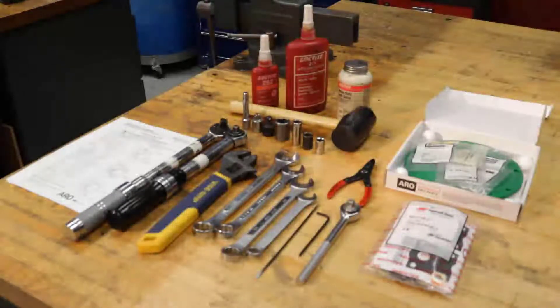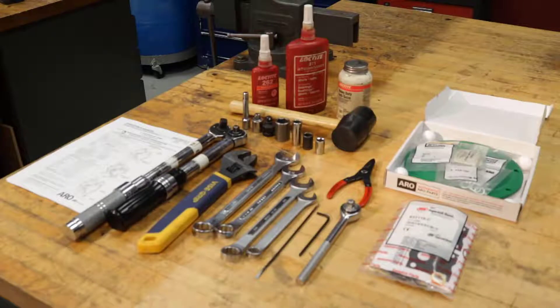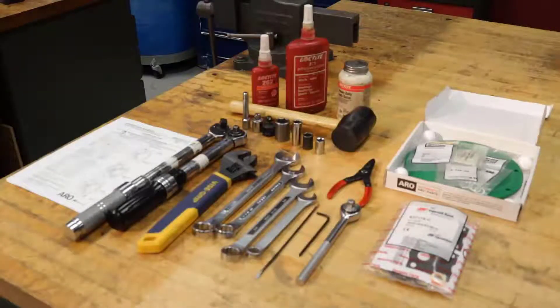Hello everyone, this is Justin and Bruce with ARO Fluid Handling Technical Support. Today we're going to be repairing a 1 inch metallic Pro Series pump. We are going to be converting a Pro Series pump with nitrile balls and diaphragms to a PTFE ball and diaphragm material. We're going to need the appropriate tools along with the appropriate Loctite and anti-seize, and you want to make sure that you always have your operator's manual and that you're using authentic ARO parts. Today we're going to be using a 637-119-44-C PTFE fluid section repair kit and a 637-118-C air section repair kit.